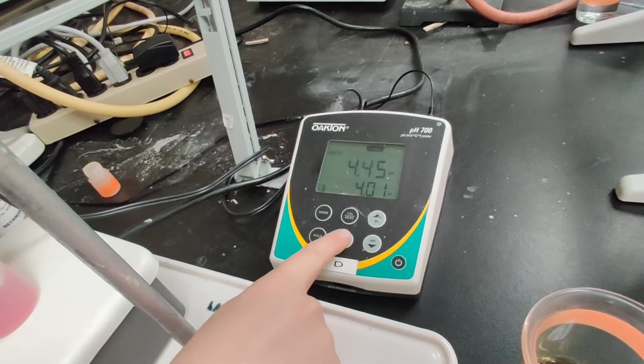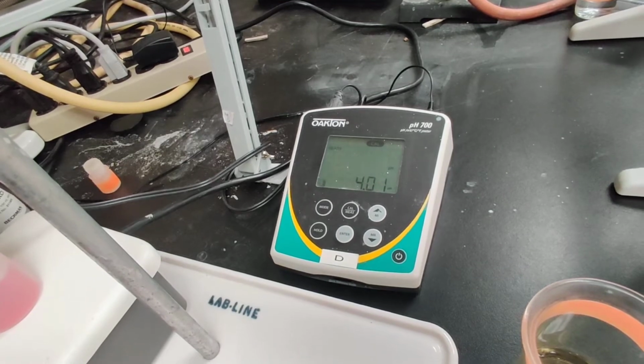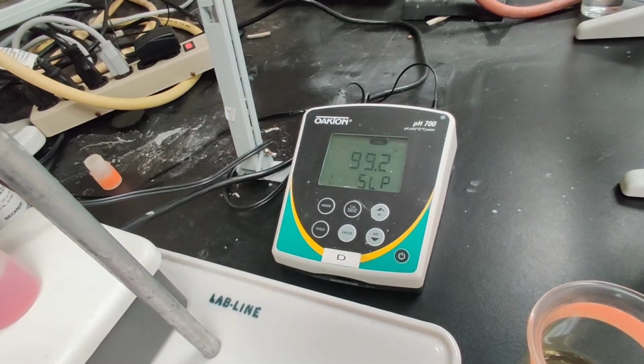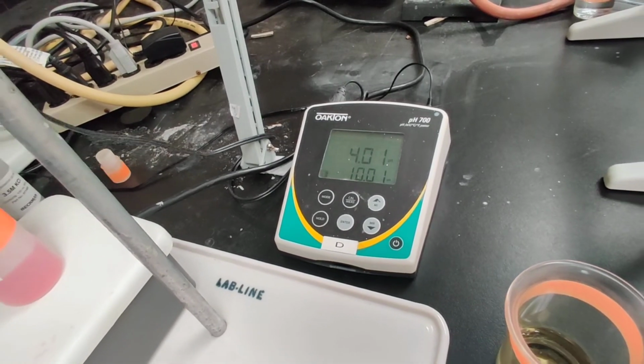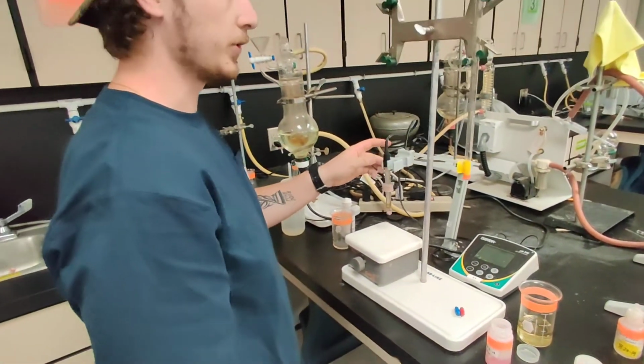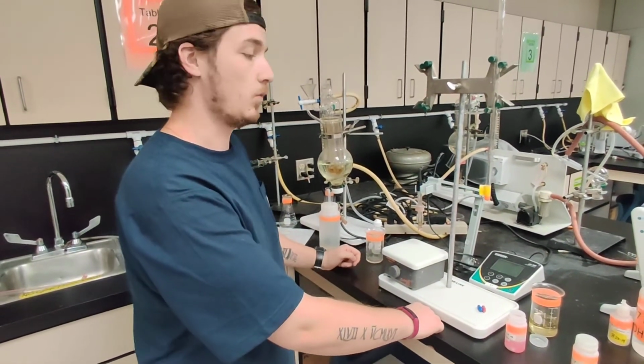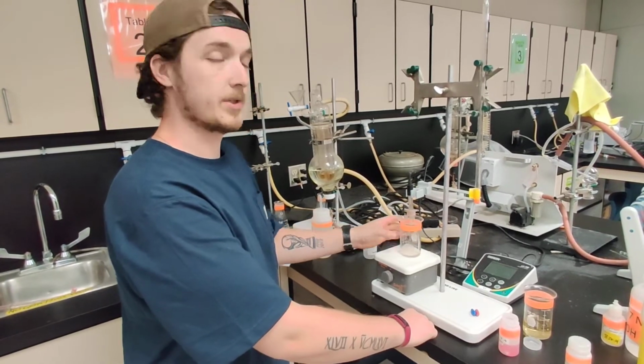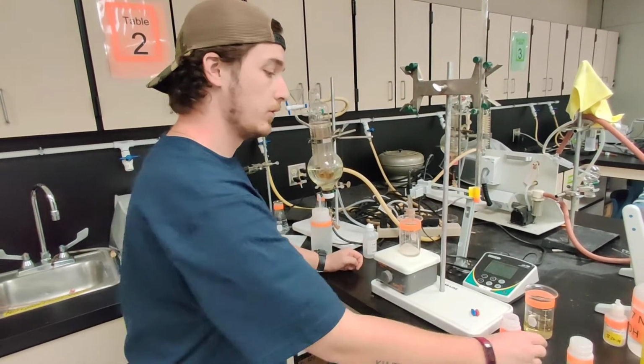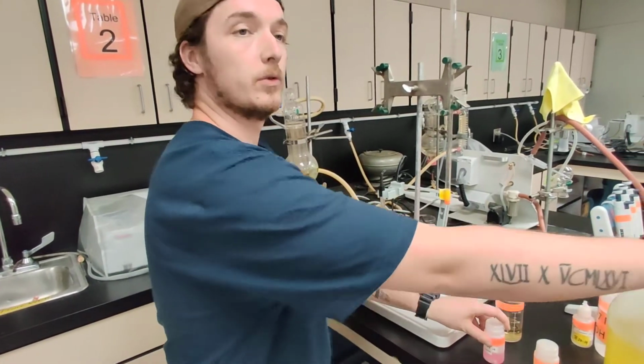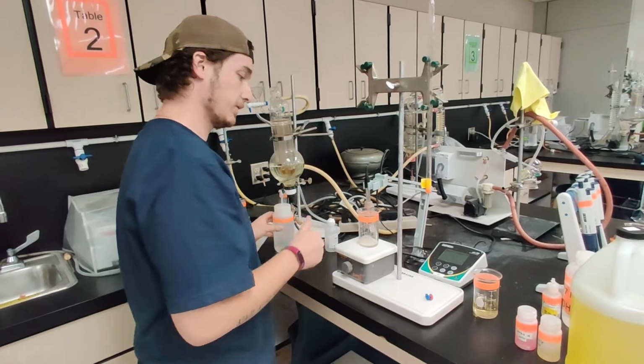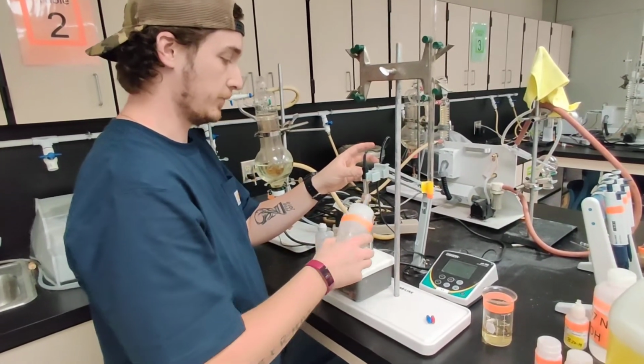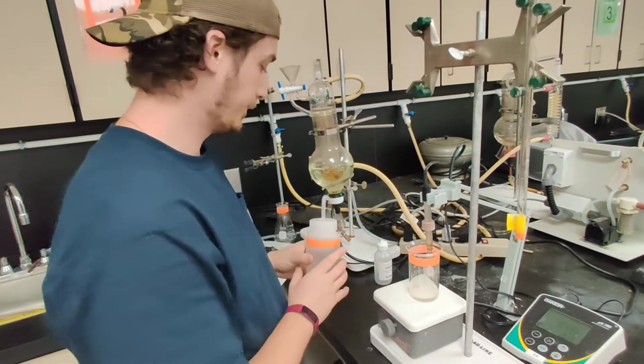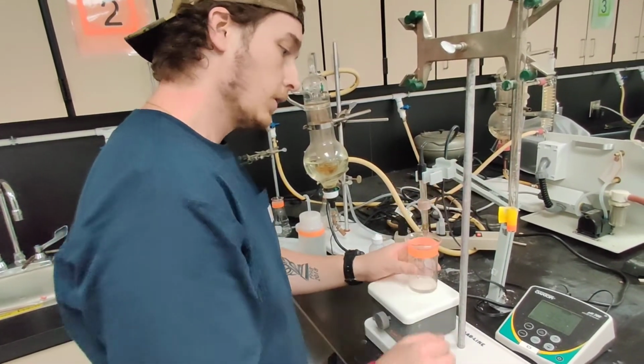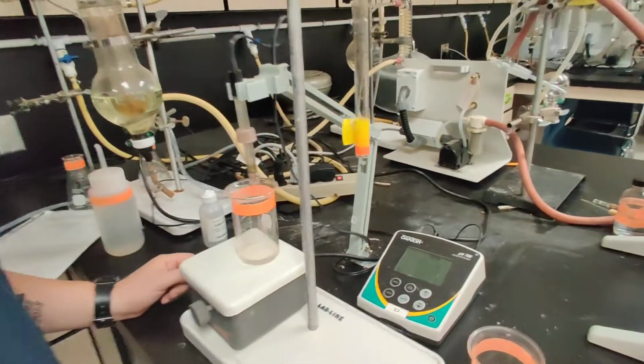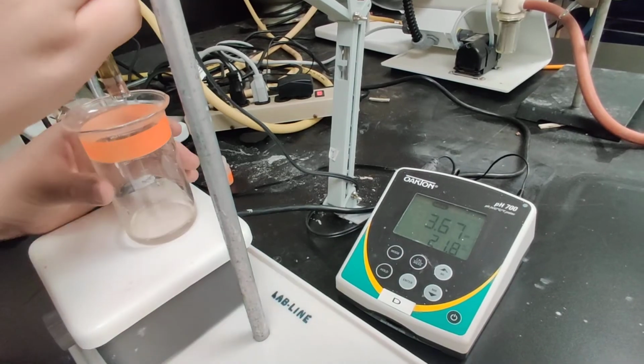It's ready, so I hit enter. And then this should give us a number, which is 99.2 at the moment. This number is what we call the slope. It's how precise your calibration was. 99% is really great. It depends on how good your buffer solutions are, but 99% is really good. That means we will get a precise measurement. We need to rinse the probe one more time. Then we'll get this back into measure mode by simply hitting the cal measure button.